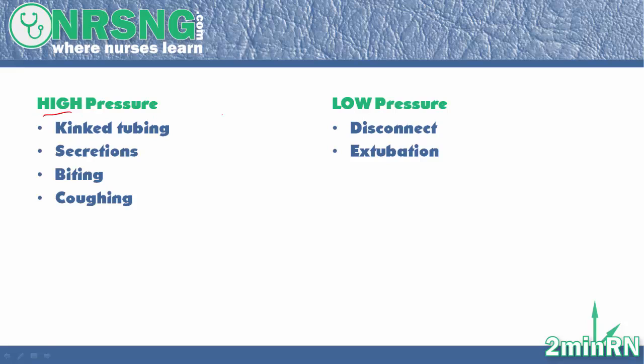First is the high pressure alarm, second is the low pressure alarm. When a high pressure alarm sounds, what's happening is the ventilator is trying to force that oxygen into the lungs and it's not able to get it in there. One cause is a kinked tube — oxygen is coming but it senses it's not able to get in there. It's pushing and pushing but there's too much pressure so it's not able to deliver that oxygen.